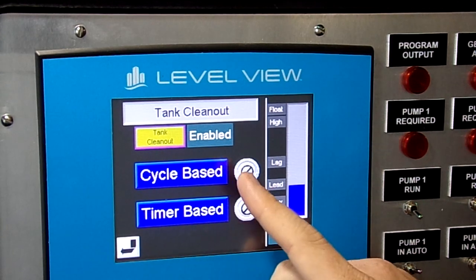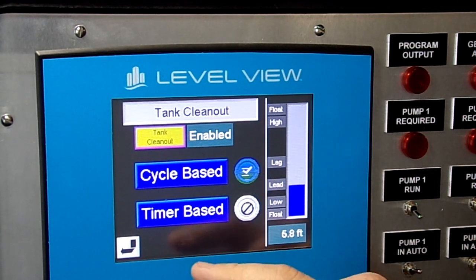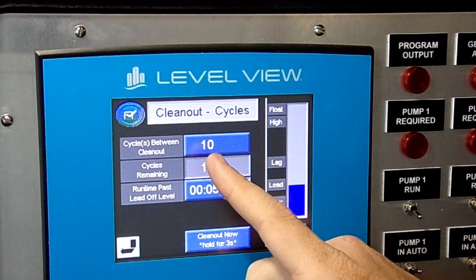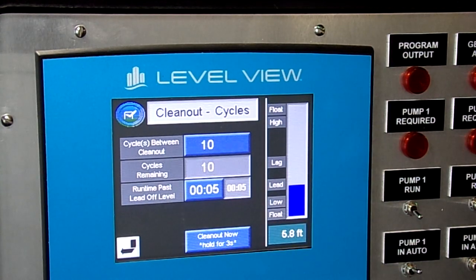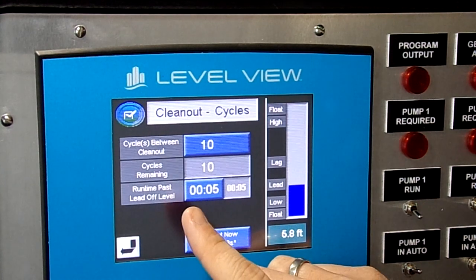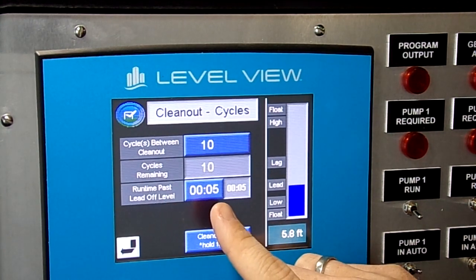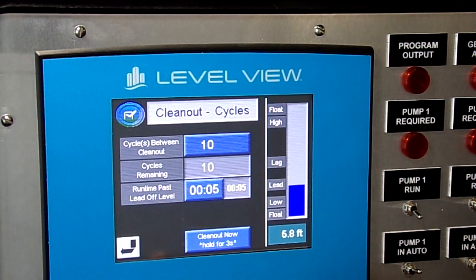We can do this based on cycles by clicking this button, and then we can run a certain amount of cycles before we run a cleanout function at our station. It also will have a runtime past, so that it'll need to be changed at startup for how long your pump needs to run before it can be shut down. The clean out now function is available also on this screen, where it can be manually forced to clean out if you hold it for 3 seconds.